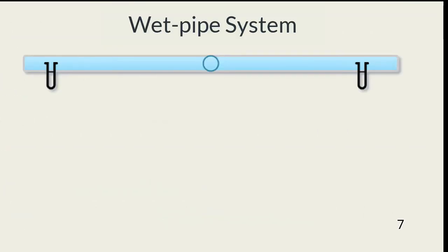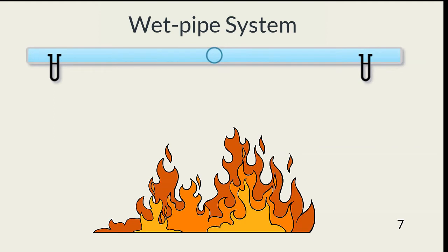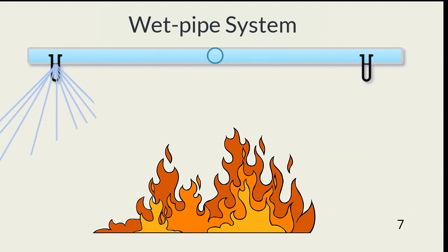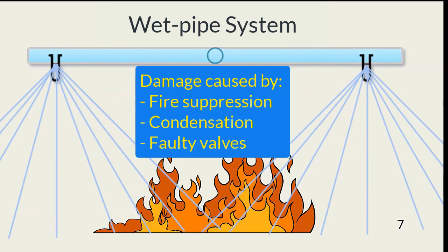Wet pipe systems are the most commonly used. The pipes leading to ceiling valves are always filled with water. When a fire causes the valves to experience a certain level of heat, the valves open. The advantages of wet pipe include low cost for installation and maintenance; they're also highly reliable and only release water closest to the fire. The problem with wet pipe is the damage water does to computer equipment. Damage can be caused by the actual release due to fire, pipe condensation, or a defective valve.